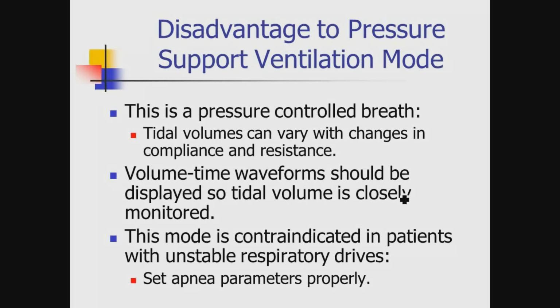If all of a sudden her lung compliance improves, I could get too big of a tidal volume. And obviously anyone who is apneic probably is not the best option to put in a spontaneous mode if they have frequent periods of apnea.